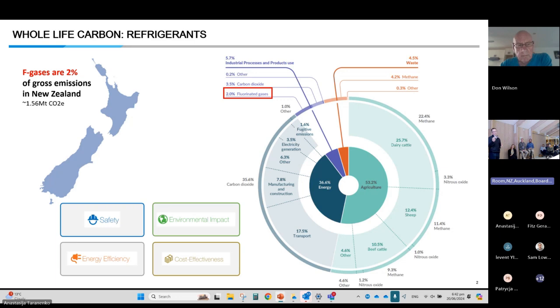When we look at different refrigerants, it's important to say that yes, we want to lower the environmental impact based on a GWP metric, but we also need to consider cost, the impact on energy efficiency, the actual thermal properties of the product, and safety. If that refrigerant was to leak, is it toxic, is it flammable, how does that impact the occupants and the environment? A few different considerations there.